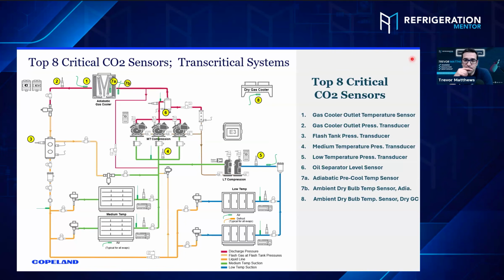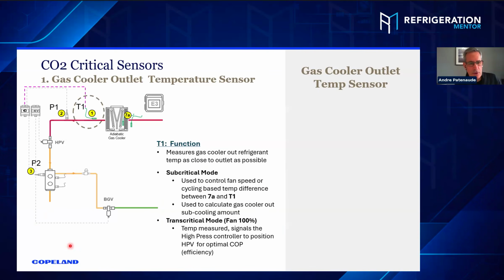So let's dive into it. Let's start here with the first one, the gas cooler outlet temperature sensor. So instead of having the whole system, let me just focus on T1. Now, when we're talking about Copeland, when we identify sensor T1, we call it the gas cooler out. So what does that thing do? Well, it measures the gas cooler outlet temperature as close to the gas cooler as possible. But when it's in subcritical mode, so it's below the 87.8 degrees, that temperature signal is used to control.